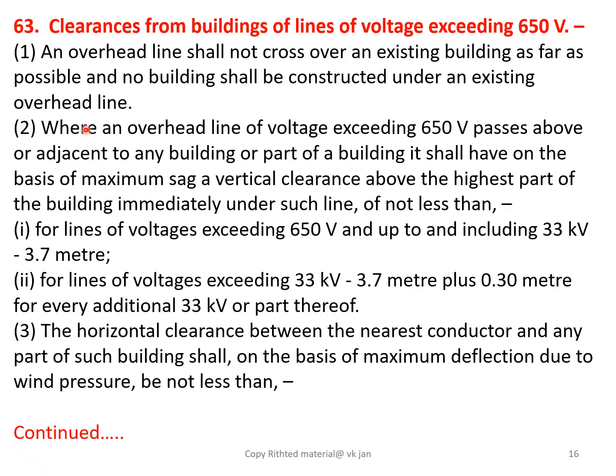Second, where an overhead line of voltage exceeding 650 volt passes above or adjacent to any building or part of building, it shall have, on the basis of maximum sag, a vertical clearance above the highest part of the building immediately under such line of not less than: first, for lines of voltage exceeding 650 volt and up to and including 33 kV, 3.7 meter; second, for lines of voltage exceeding 33 kV, 3.7 meter plus 0.3 meter for every additional 33 kV or part thereof.